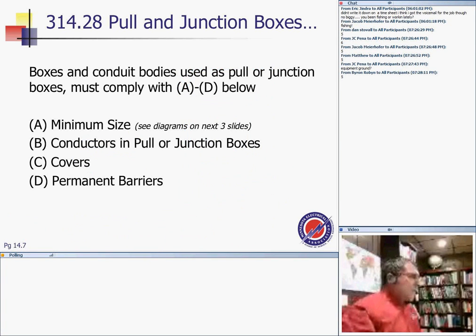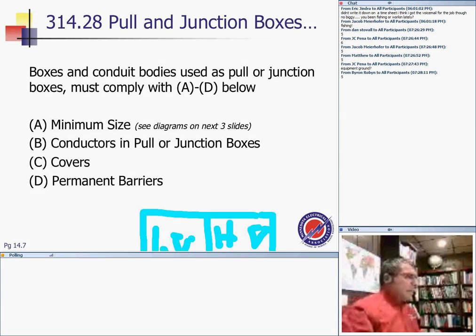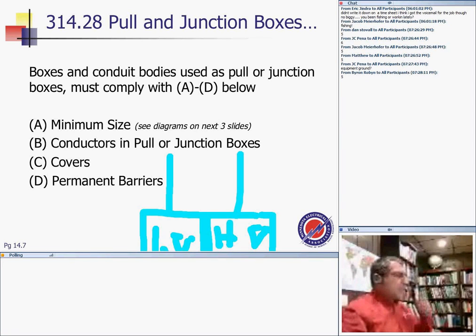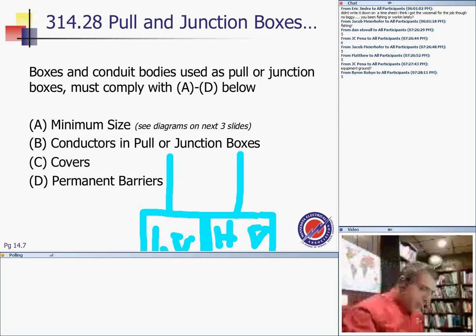Minimum sizes, raceways contain. We'll talk about the minimum size conductor for pull boxes, the covers. All junction boxes have to have a cover, and where permanent barriers are installed in boxes, each section shall be considered as a separate box. A couple of things on barriers, guys. You might be in a situation where you have to separate the boxes. I have low voltage on this side and high voltage on this side. It's okay, no problem. You have a permanent barrier between them, and you bring your conductors and conduits from both sides to take both systems. Each one of them will be considered a different box with a barrier. You need a cover for everything.